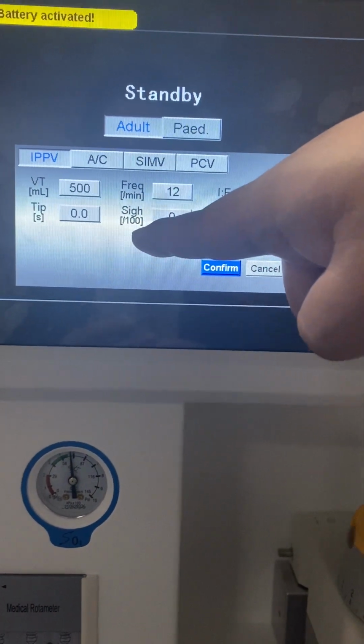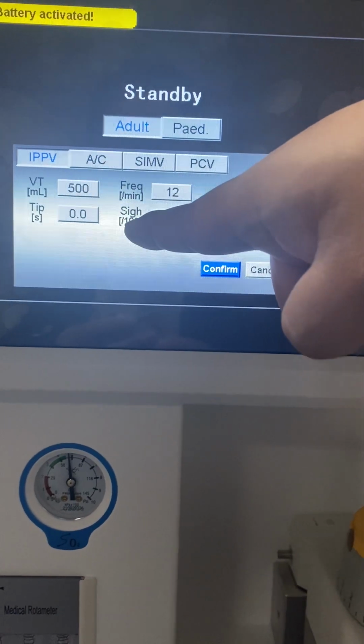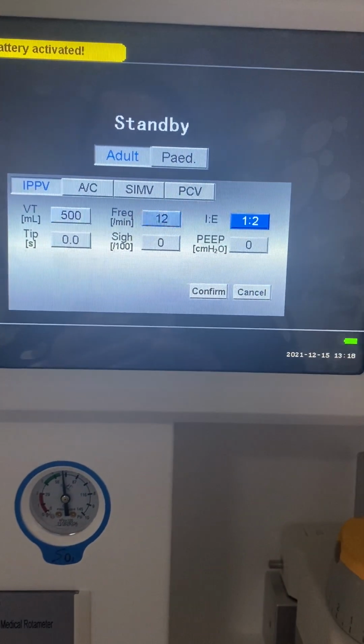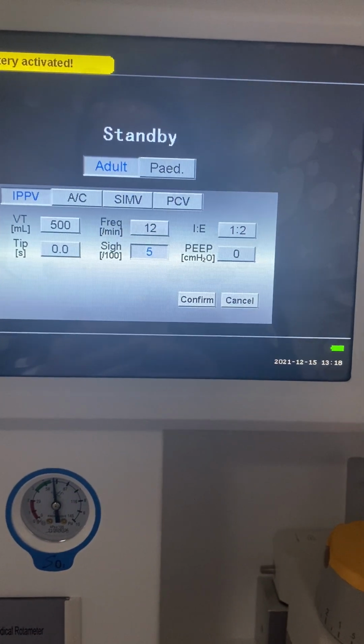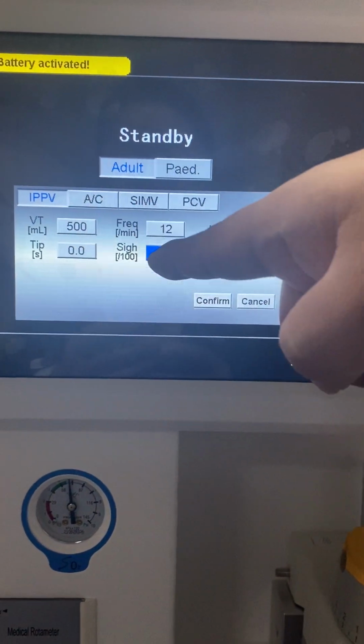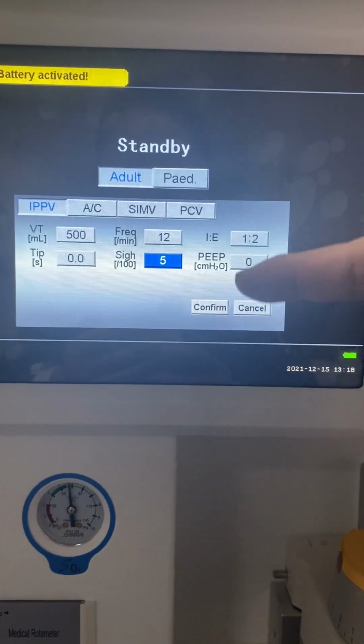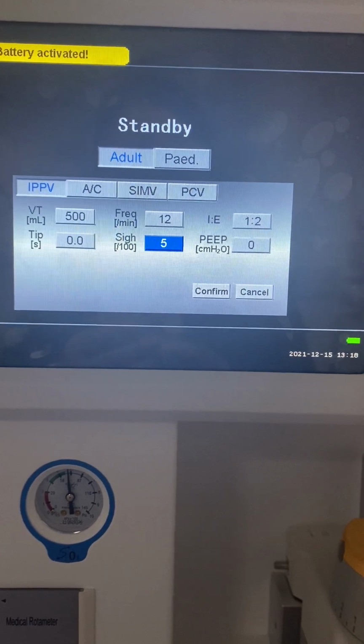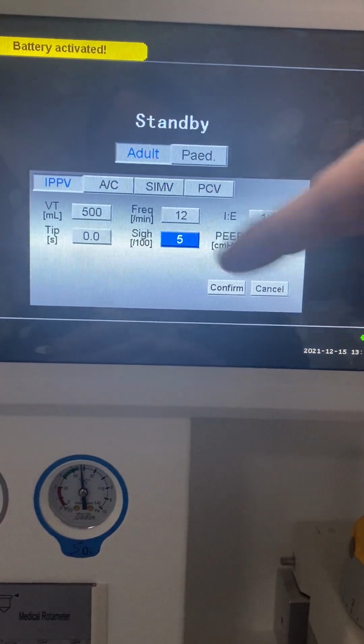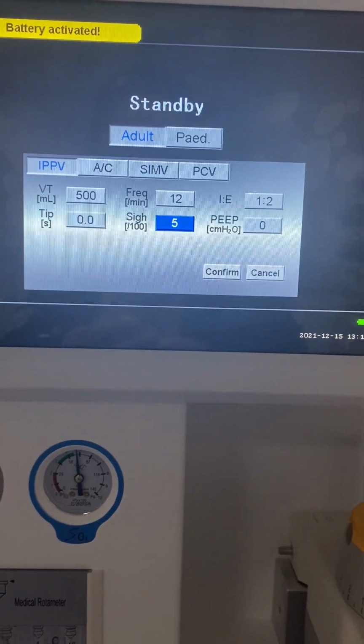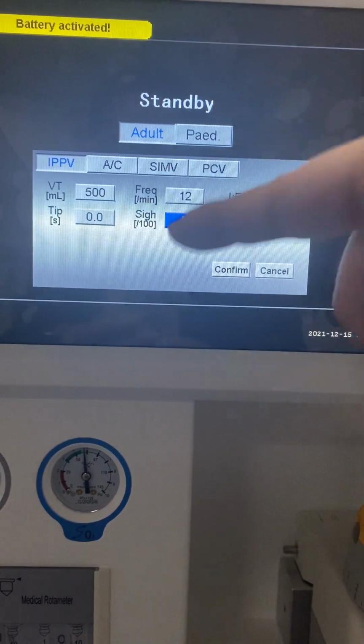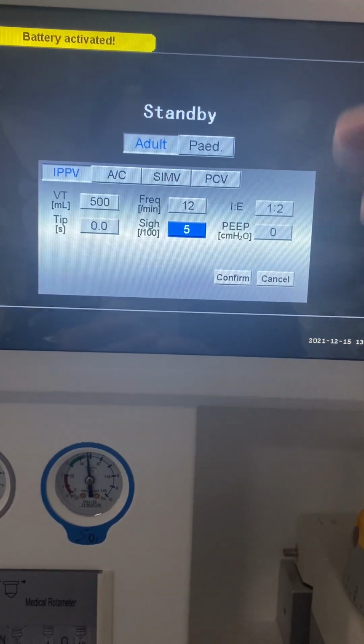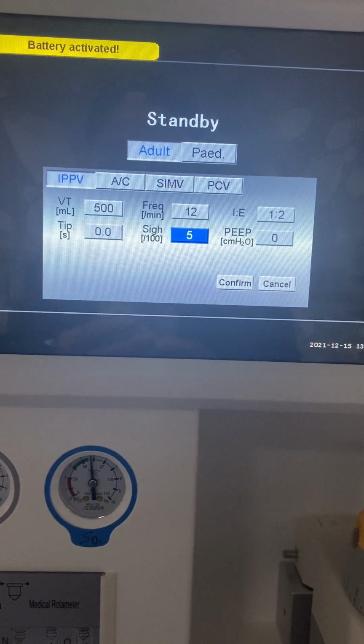So what is sigh? You can see here it has a parameter out of 100. For example, if I set it to 5, it means 5 out of 100. So in the next 100 breathing cycles, it will give 5 long breaths. The counting is every 20 breathing cycles, and it will give one deep breath.